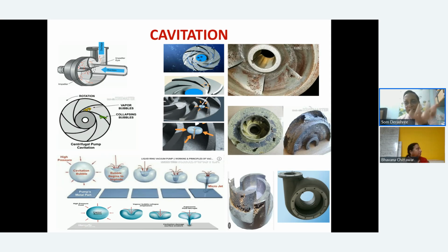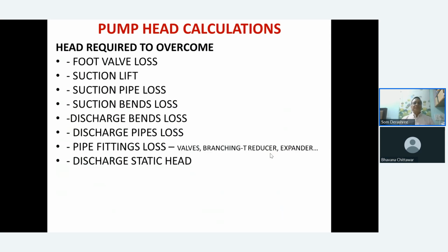Now this will even change the characteristic of the pump, which was originally there. You don't know, the pump is running. I've seen a horrible condition where almost the whole impeller is eaten up. The pump is running, so they say, okay, cooling tower, one more pump you run. So they run two pumps. It is eating up energy, not pumping anything. And that is the situation which happens.